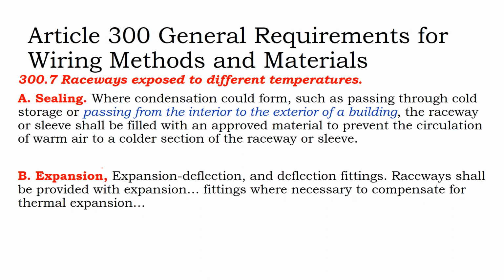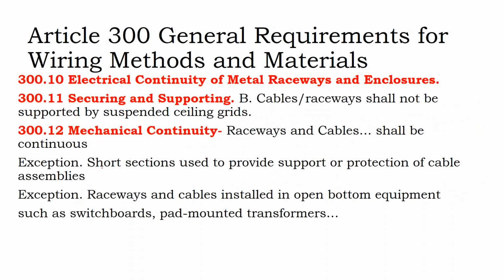The expansion fittings where necessary to compensate for thermal expansion. And so, if your solar arrays become sufficiently long, I think it's something like 120 feet or longer, that rail is going to be giving you some rather substantial expansion and contraction up on the rooftop. You need to use expansion fittings on your conduit so that you don't pull your fittings out of your box.